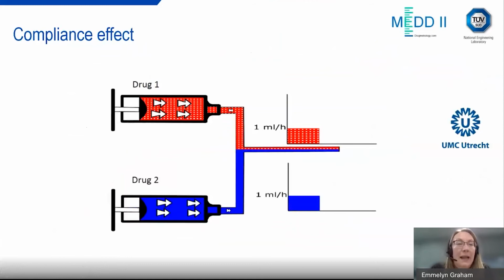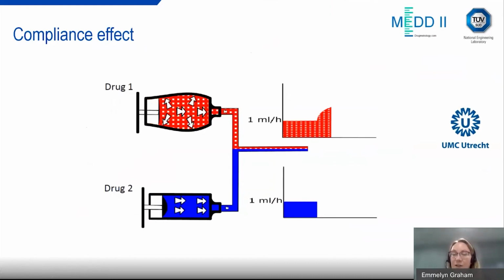If we look now at the compliance effect, what we see here is we've simplified this down. So we've got our red drug and our blue drug, and these are both flowing out at 1 milliliter per hour. So at the same flow rate, they're going into the mixed infusion line and traveling at the same velocity. Then if one of the drugs has its flow rate increased or doubled, what happens first of all is we have a compliance effect where the syringe and other components can expand and absorb that increase in the flow rate and the increase in the volume that should be pushed out. So we can see in the graph at the top, there's not an instantaneous increase in the flow rate. It's quite gradual and it builds up the flow rate because of this compliance effect.